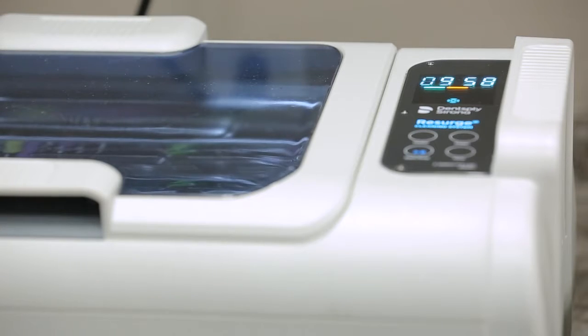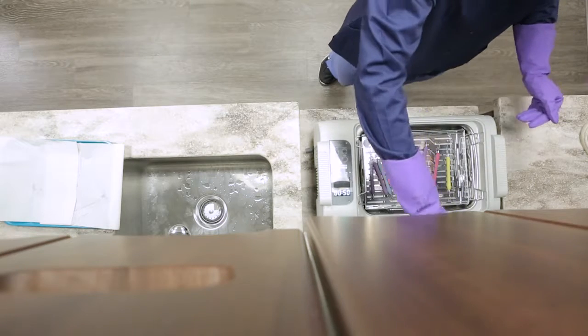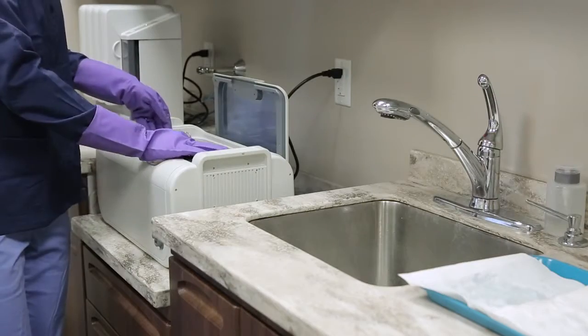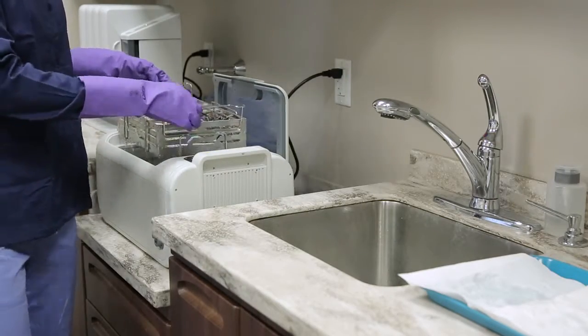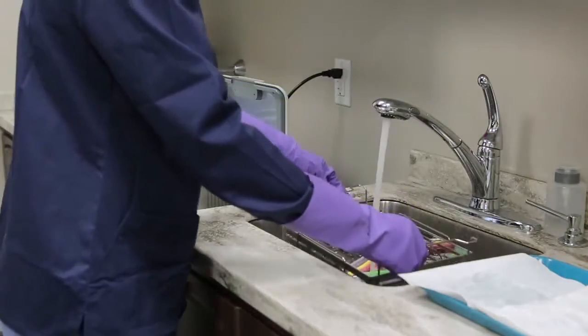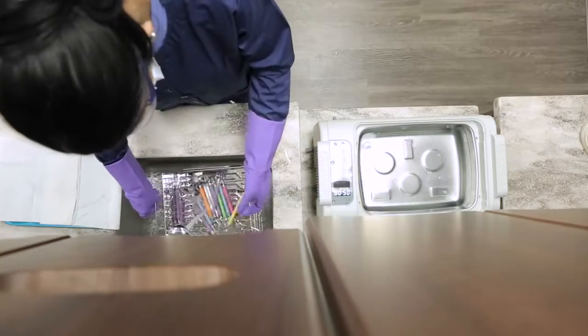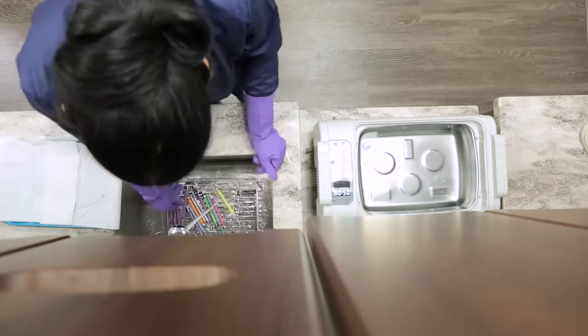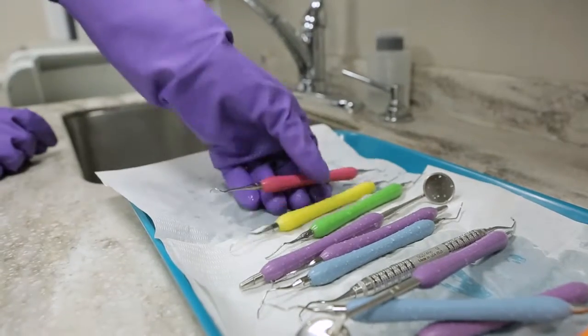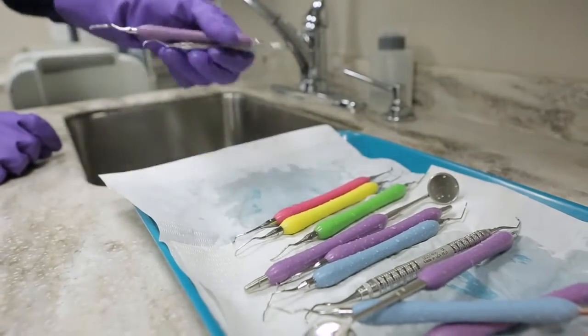Once the cycle ends, remove the lid and place it in the convenient holder on the back of the unit. Lift up the universal rack and allow excess liquid to drain off the instruments. Rinse the instruments to remove any residual instrument cleaner. Lay on towel to dry in preparation for autoclaving.